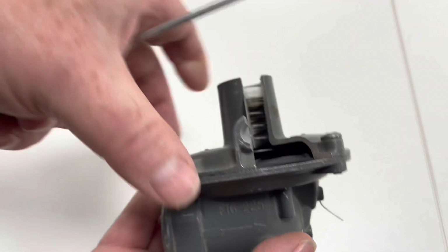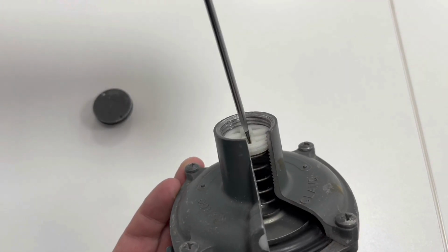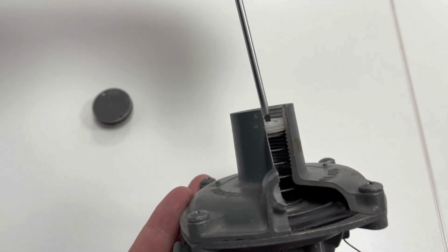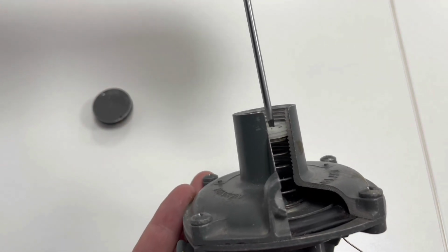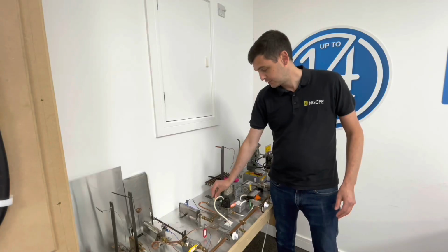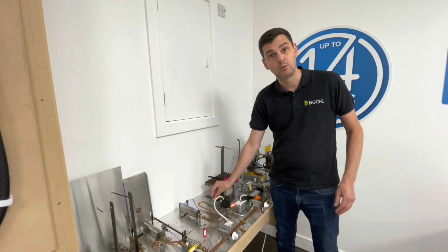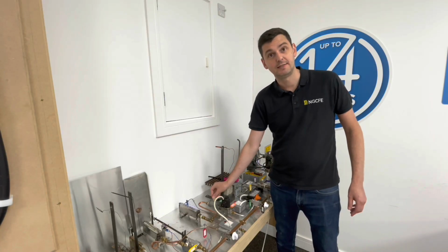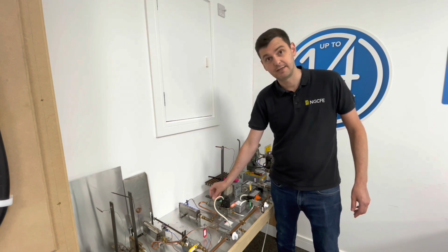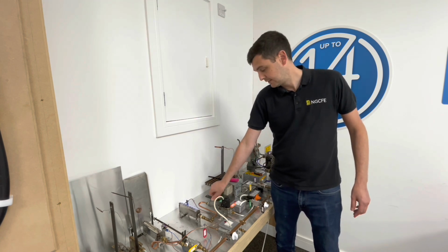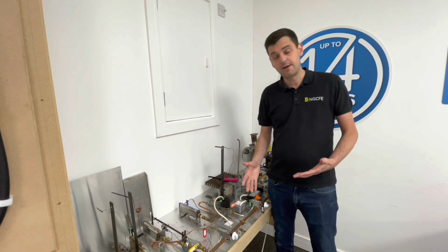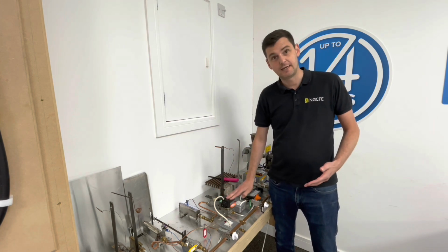We can adjust the setting of the spring, which will then apply more or less force on the diaphragm, so that we can alter that outlet pressure. So how we would test it is we would take a working pressure after the outlet of the regulator. So there we have two controls in their own merit: low pressure regulator and a solenoid valve.